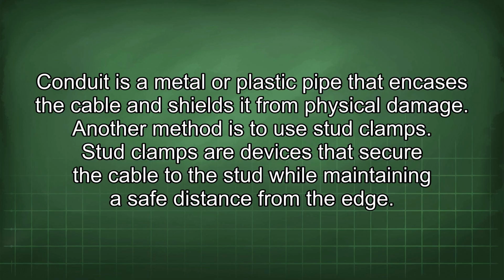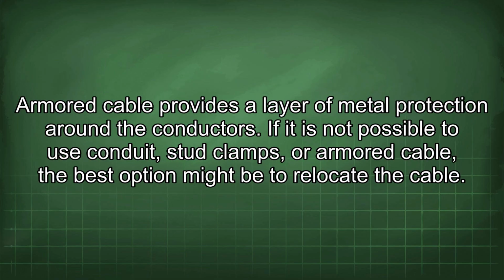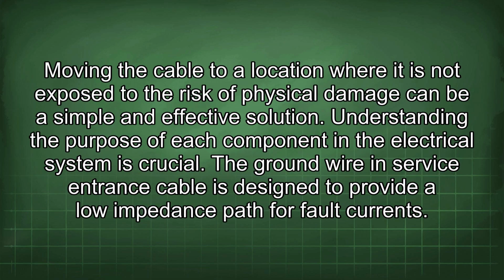Another method is to use stud clamps. Stud clamps are devices that secure the cable to the stud while maintaining a safe distance from the edge. Armored cable provides a layer of metal protection around the conductors. If it is not possible to use conduit, stud clamps, or armored cable, the best option might be to relocate the cable. Moving the cable to a location where it is not exposed to the risk of physical damage can be a simple and effective solution.